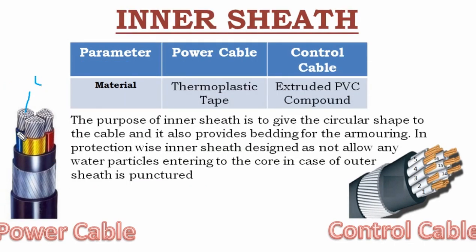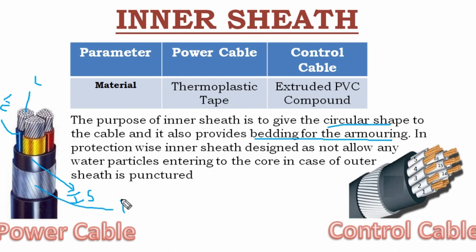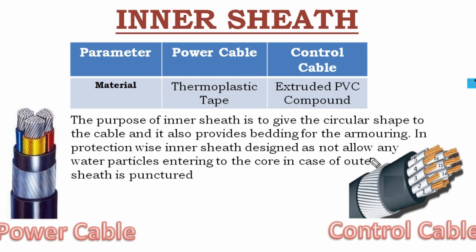Now we will learn about the inner sheath. The purpose of the inner sheath is to give a circular shape to the cable and to provide bedding to the armor. For protection, the inner sheath does not allow water particles to enter the cores in case the outer sheath is punctured. The inner sheath material for the power cable is thermoplastic tape, and for the control cable it is extruded PVC compound.